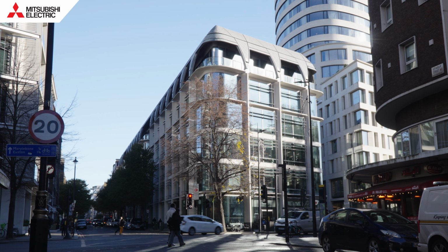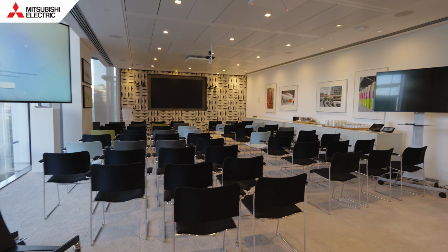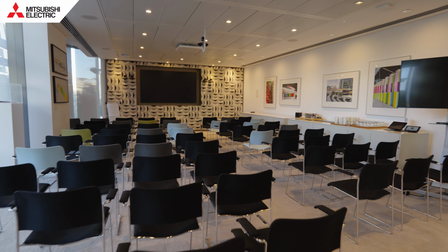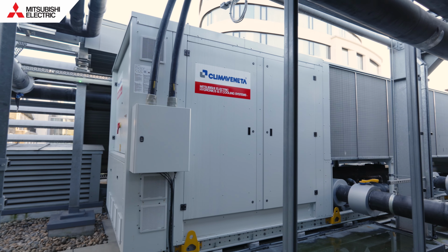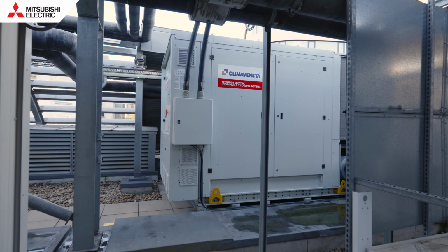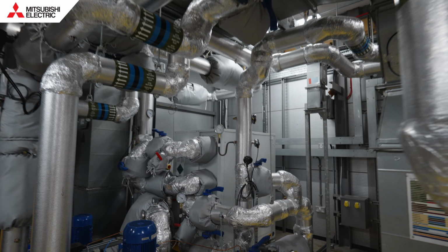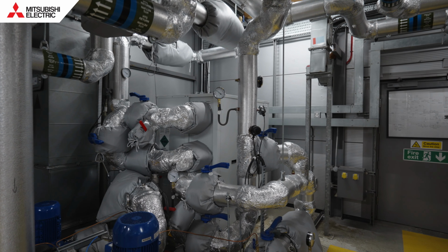As part of the project here, we engaged an advanced building model in line with the NABERS standard to identify what the peak loads would be. So we came up with a principle and proof that we could utilise 95% peak loads to minimise the equipment size, but also to optimise the project costs as well. So we can start controlling the building on what's called a demand-driven strategy. We don't allow the building to get cold, which reduces the time needed to heat up, and allows us to maximise the heat pump technology.